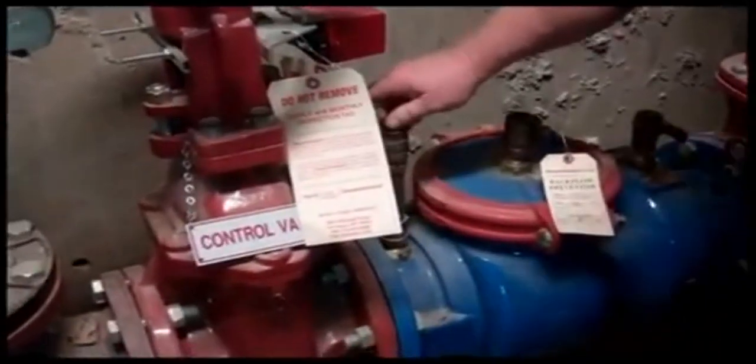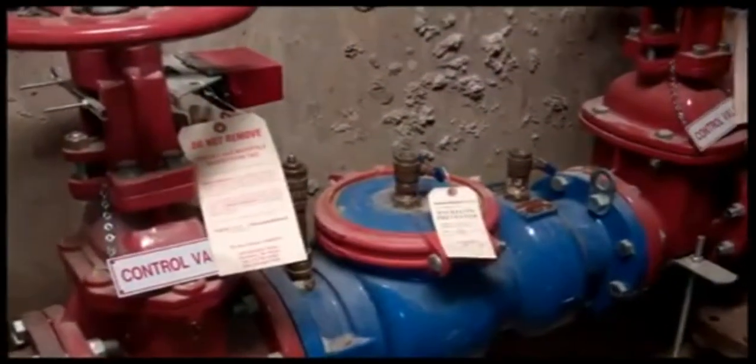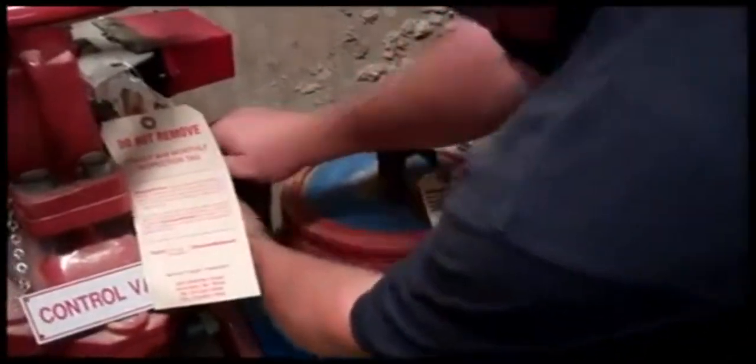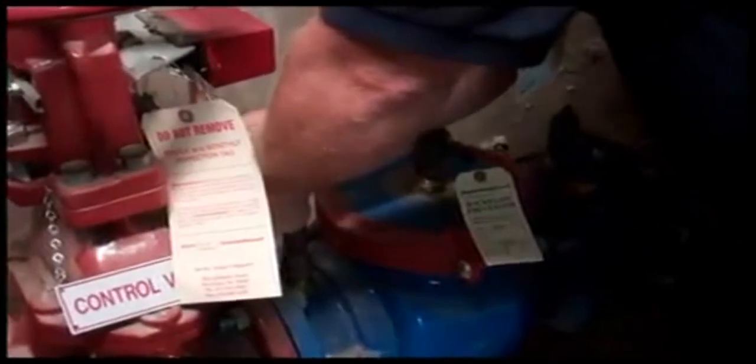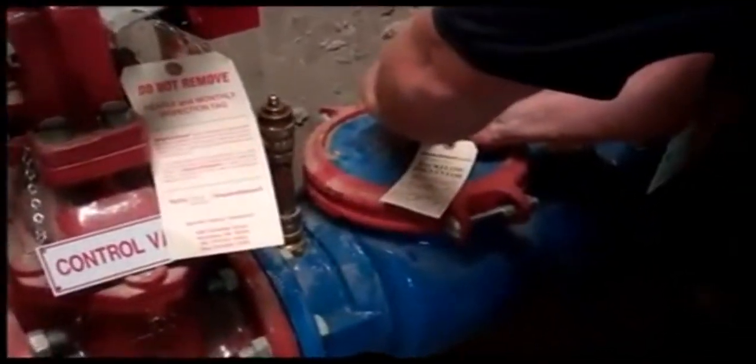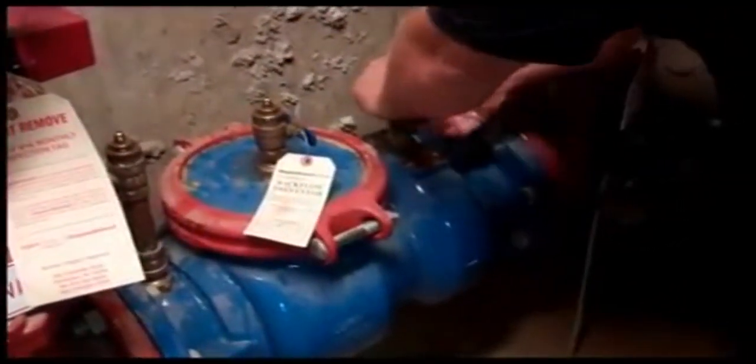The technician will then install adapters onto the test ports of the backflow device so that the testing meter can later be attached. Prior to connecting the testing device, the technician will briefly open the water supply at each test cock to make sure that any debris or dirt is blown free.